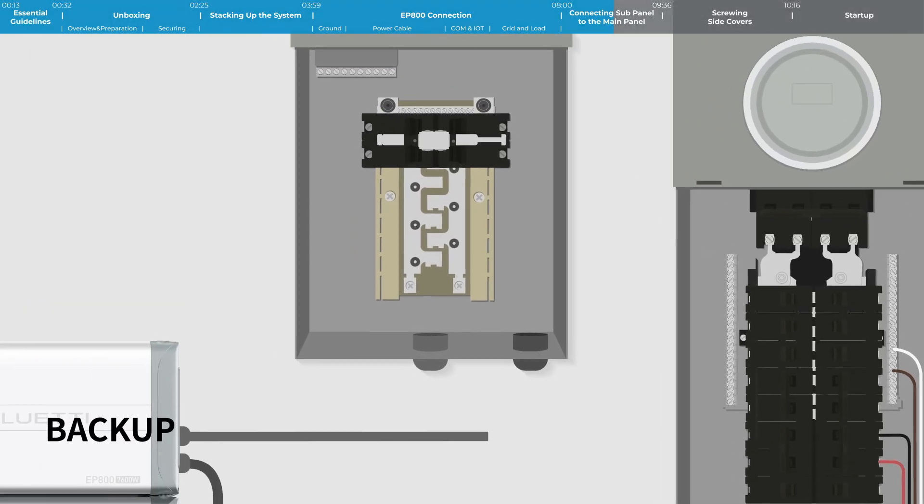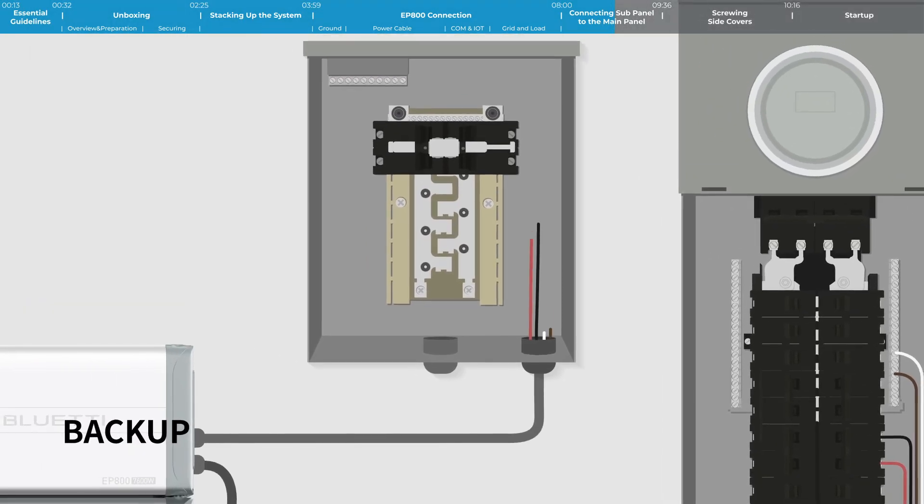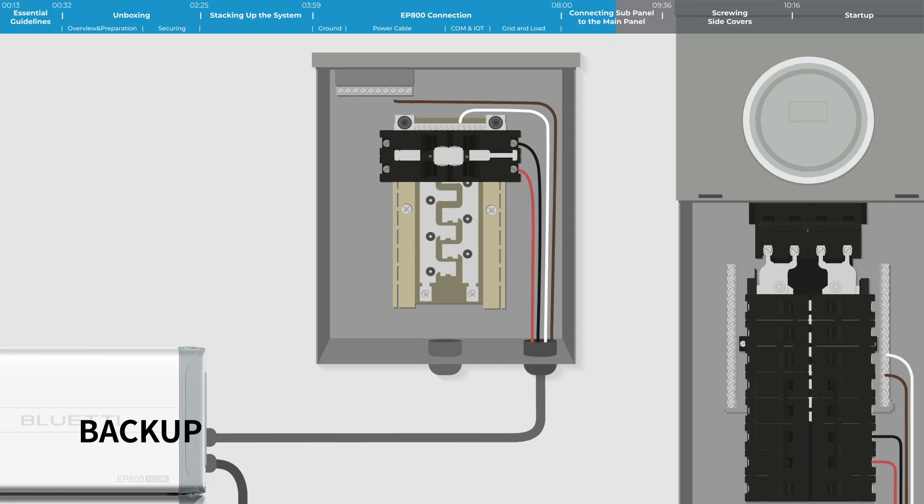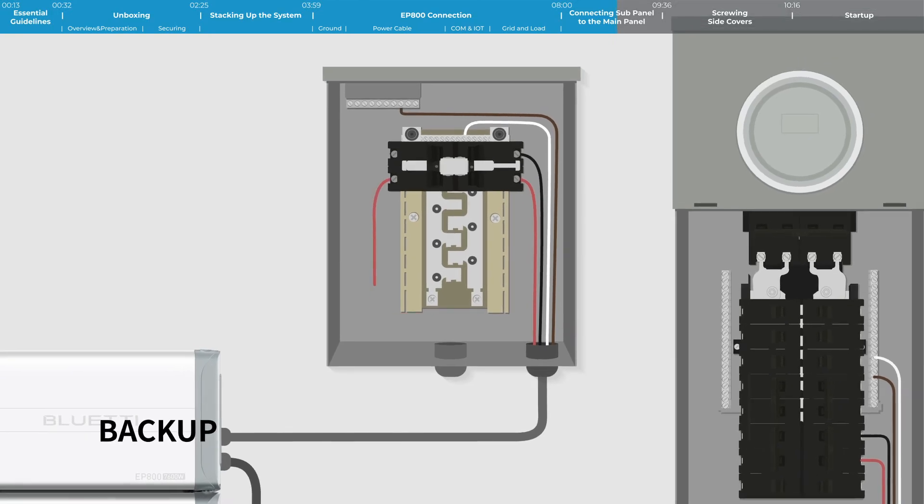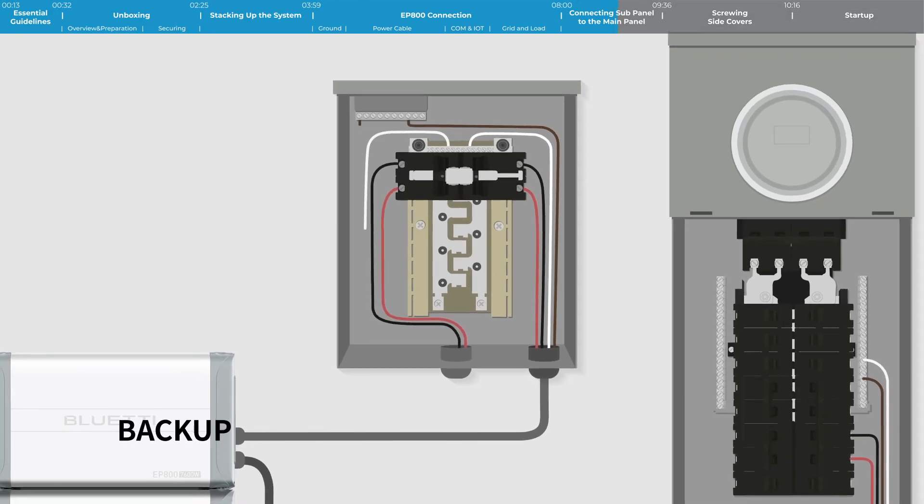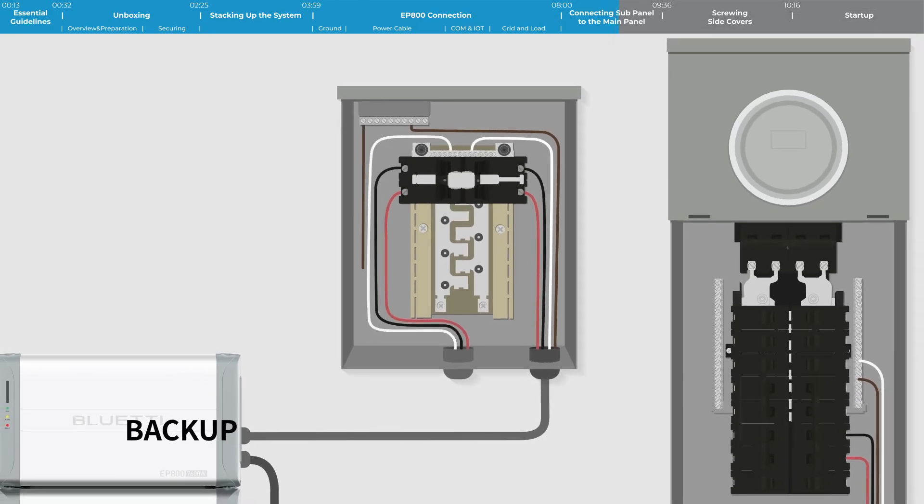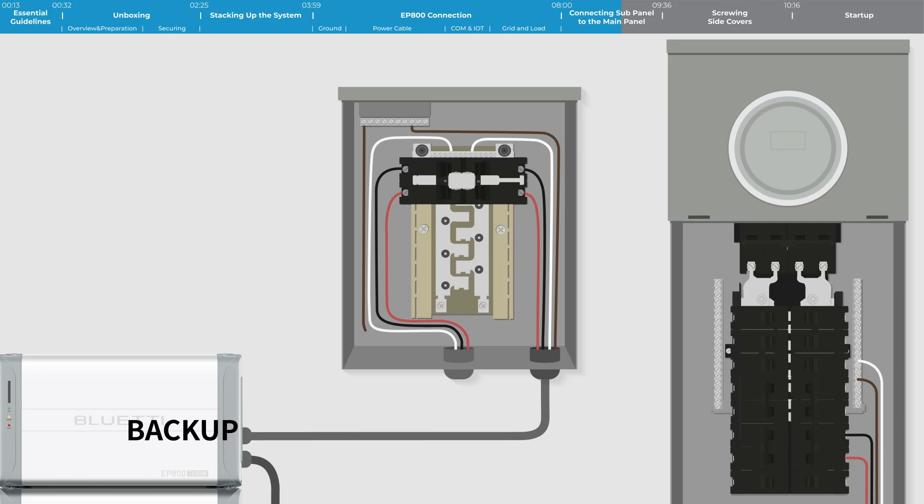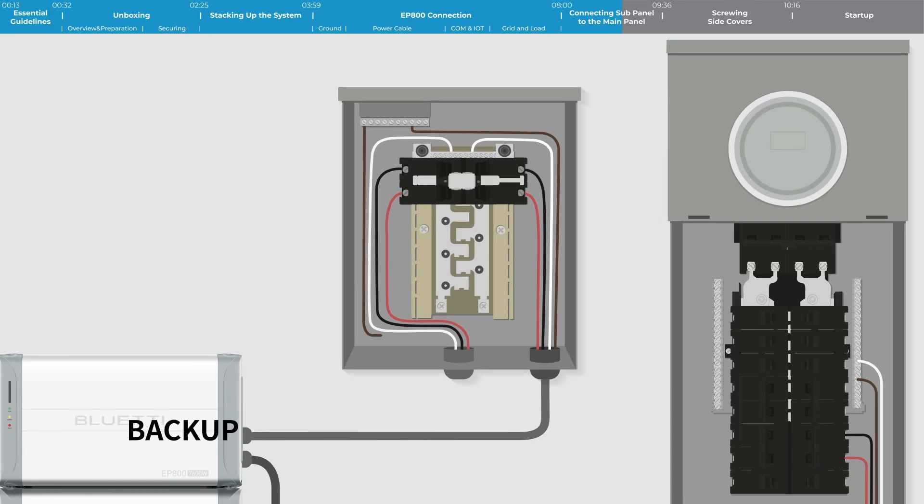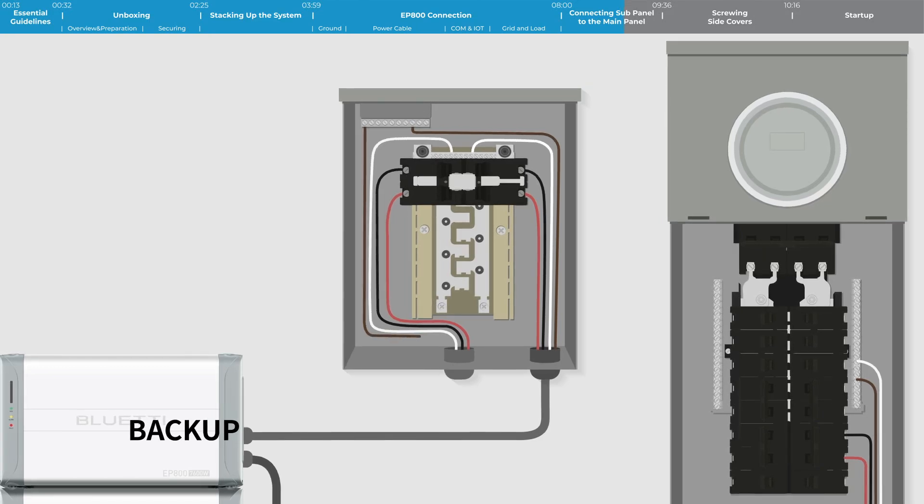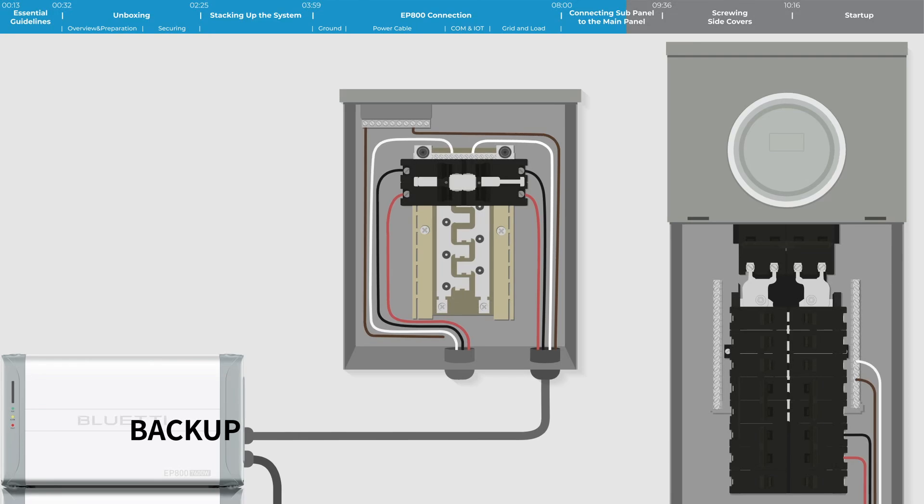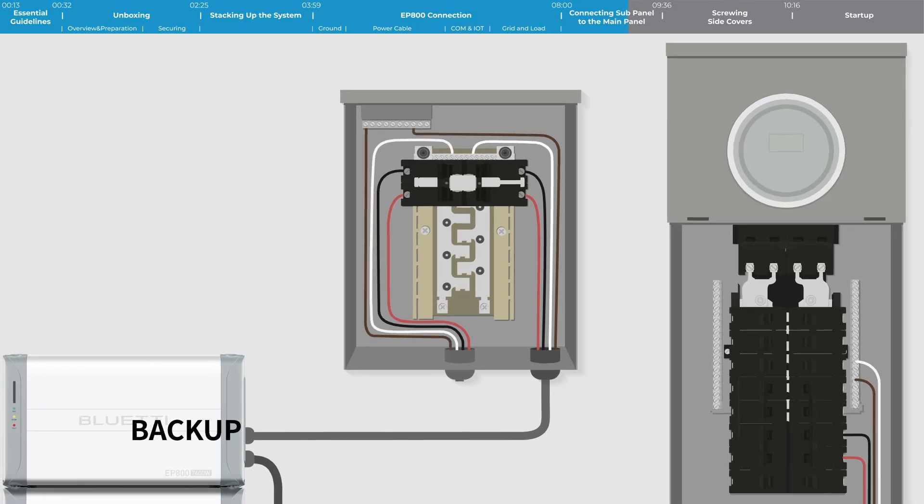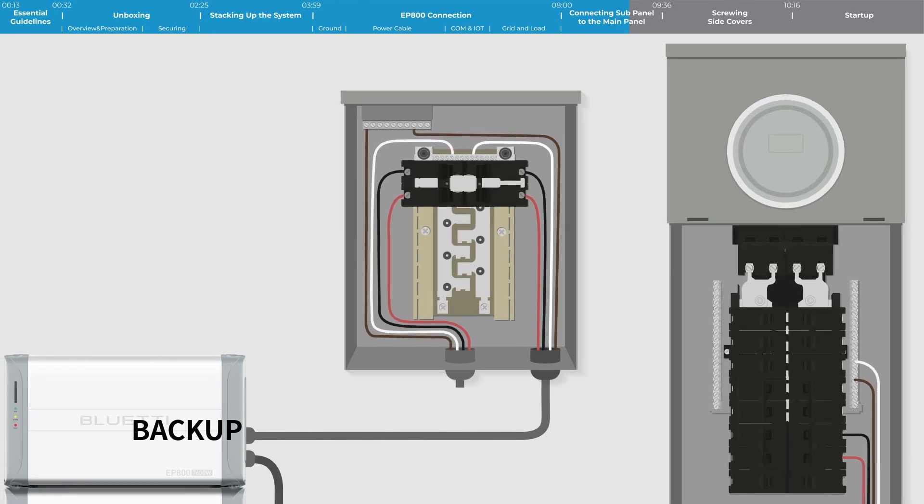Take the EP800's backup cable to the sub-panel. Connect the live wires to the left side terminals of the transfer switch. Attach the neutral wire to the neutral bus bar. Connect the ground wire to the ground bus bar.